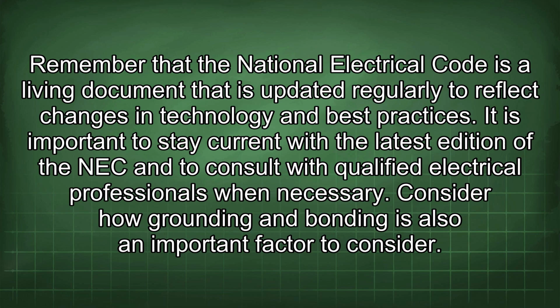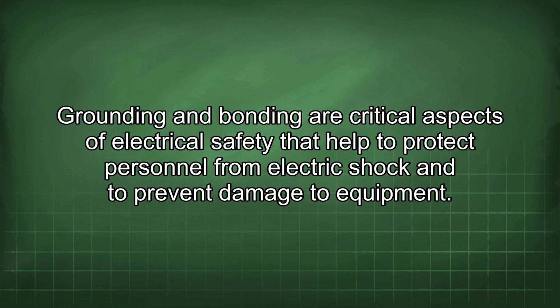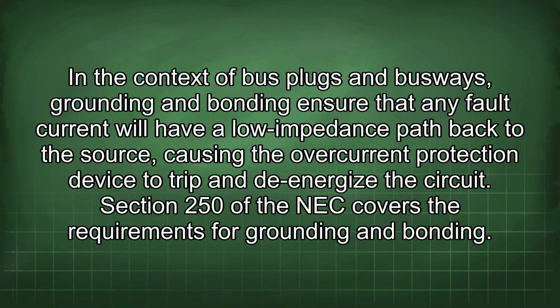Consider how grounding and bonding is also an important factor to consider. Grounding and bonding are critical aspects of electrical safety that help to protect personnel from electric shock and to prevent damage to equipment. In the context of bus plugs and busways, grounding and bonding ensure that any fault current will have a low impedance path back to the source, causing the overcurrent protection device to trip and de-energize the circuit.